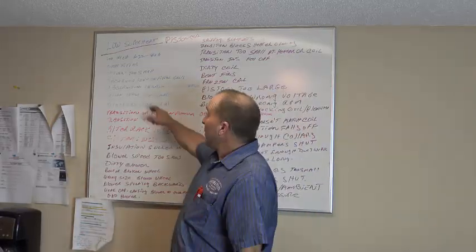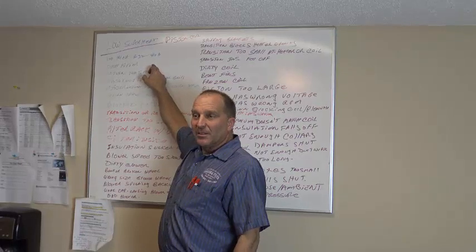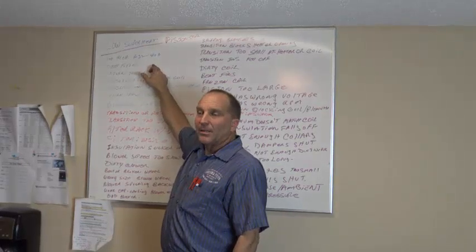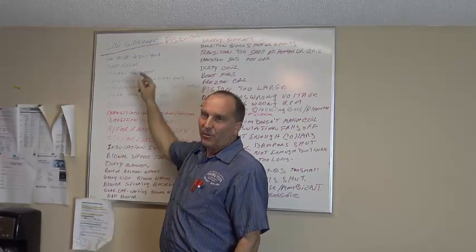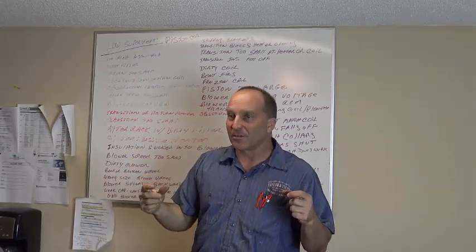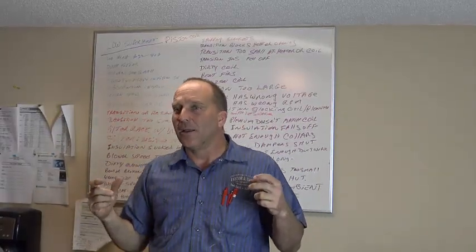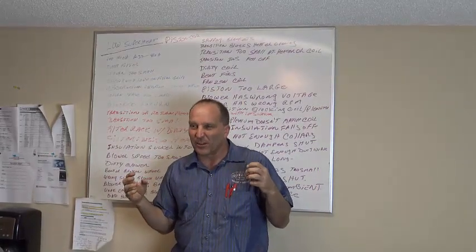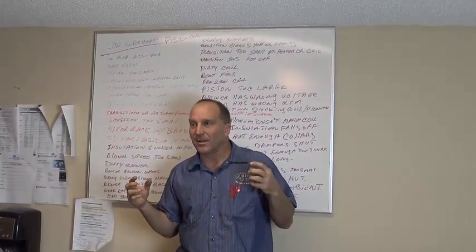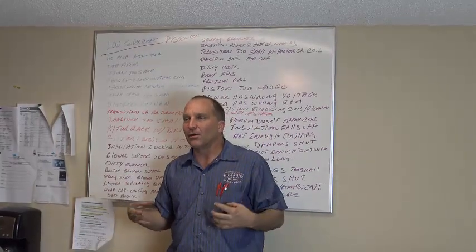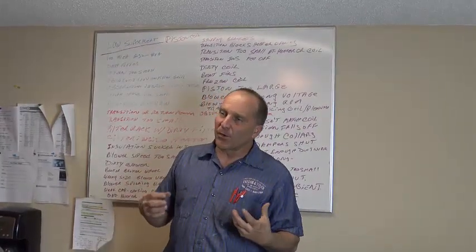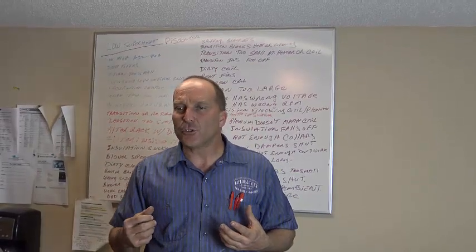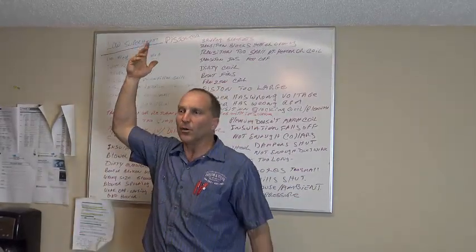One of the things we didn't mention, we said dirty filter. You know what we didn't say? An electrostatic filter. They're real thick filters. Okay? People, they'll buy those really allergy-free filters that are really thick. Now what that did was it restricted the airflow through the system. Those filters are fine, but you better increase the size of your filter grill.